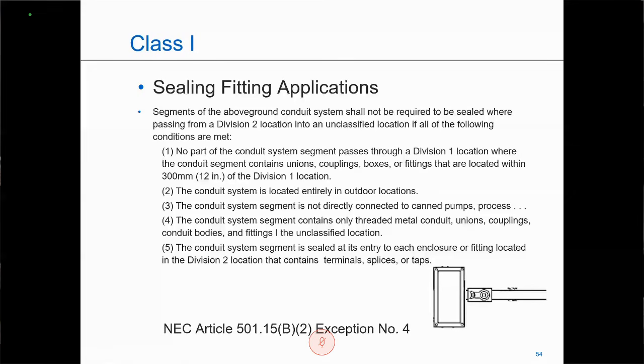I did see a question come up as far as sealing between 2 units, and that's normally a slide I have, so I apologize if that slide somehow may have gotten hidden. But to answer that question, if I have 2 explosion-proof units, traditionally you would think they each require a seal. But if those 2 units are 36 inches or closer, I can put one seal in the middle, and now I'm within 18 inches of each unit. So that one seal would do.